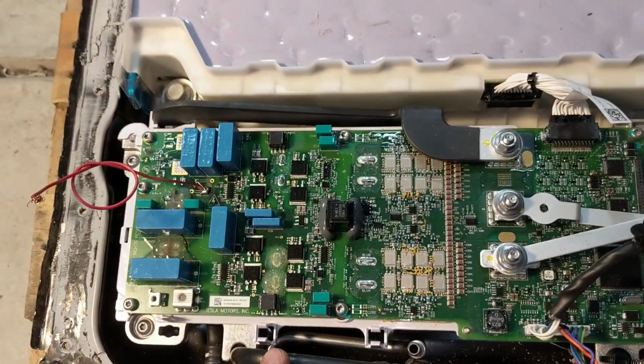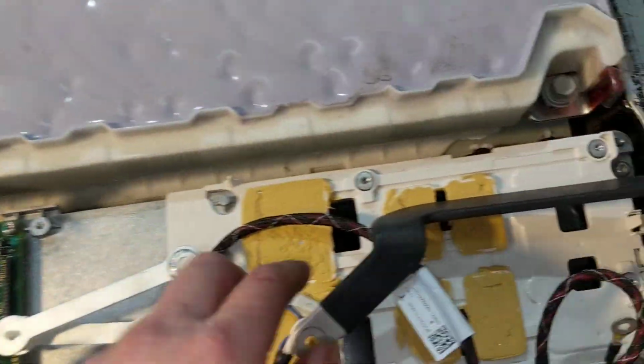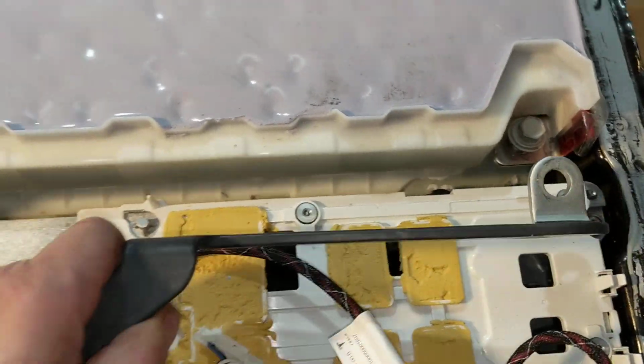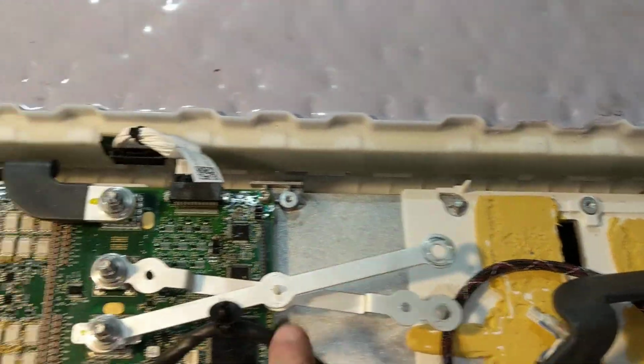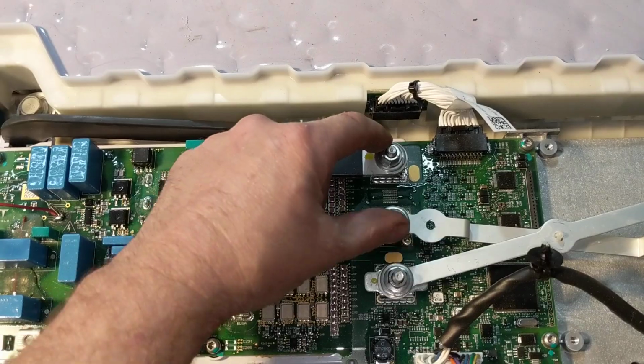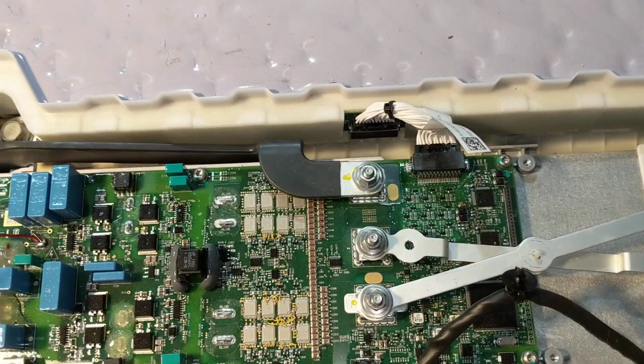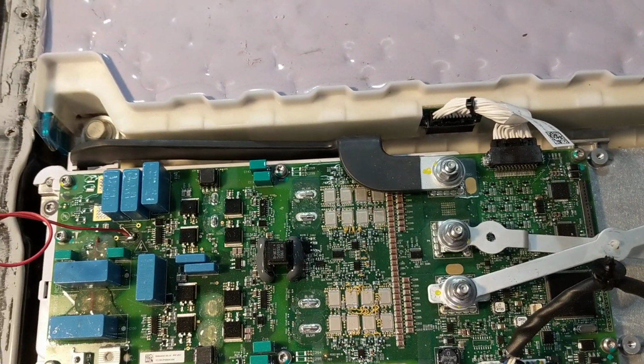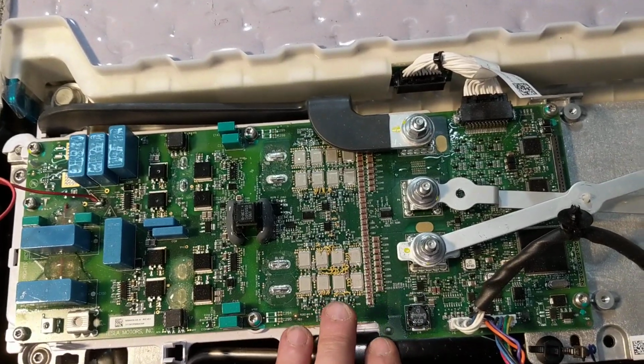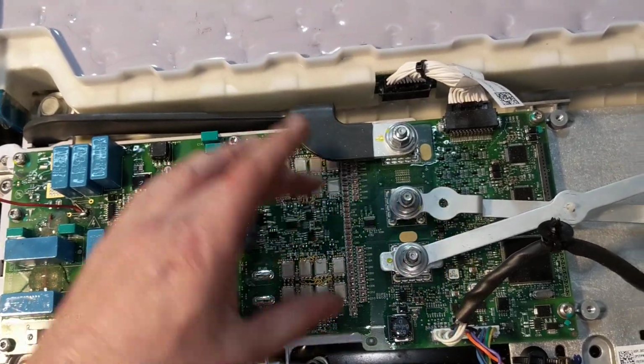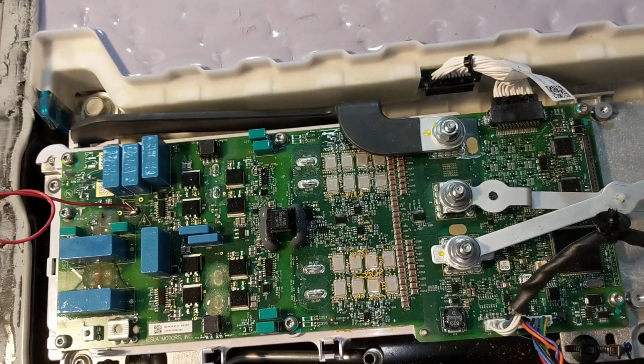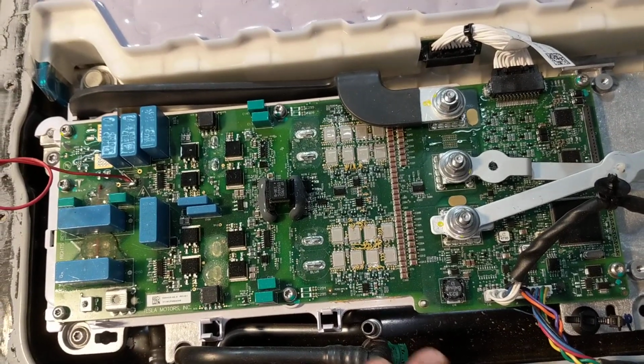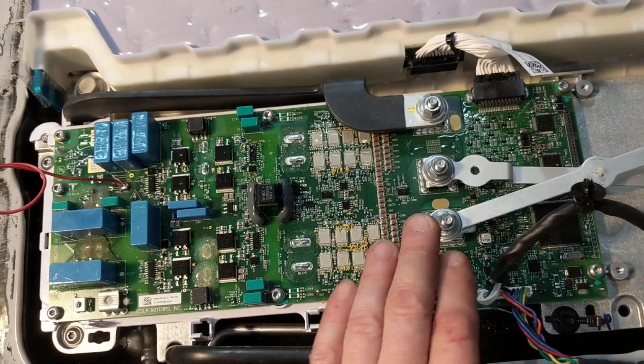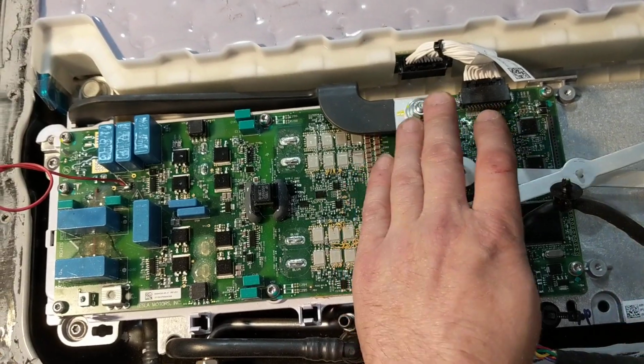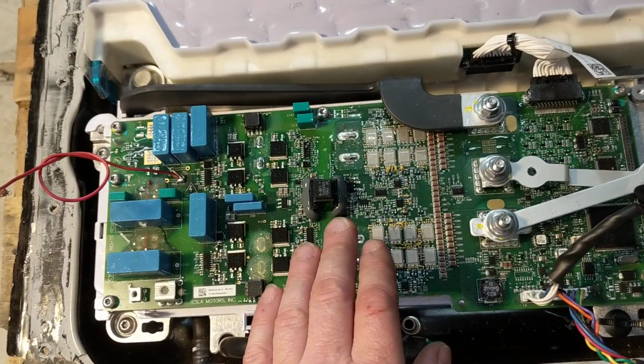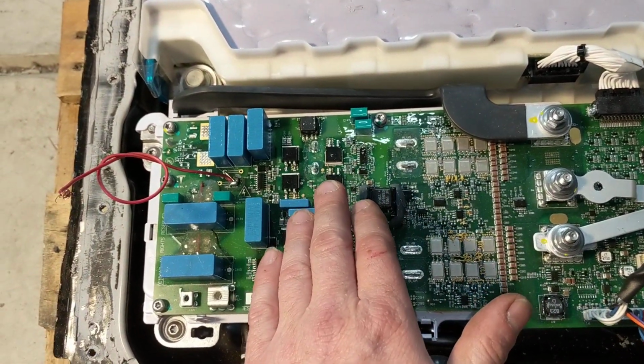What this thing is doing is taking the 48 volts, normally that's one of the terminals, this bus bar goes here, and then transfers power over to this. There's a current shunt here, so it can measure the current going in and out of the battery. This system has transformers in it. There are 2 sections, I believe about 1.5 kilowatts each, that can take the 48 volts from the batteries and convert it into about 400 volts DC.